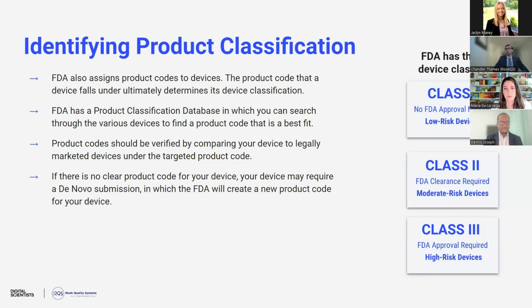Once you've identified a product code, you want to verify it by comparing it to legally marketed devices under the targeted product code. If you have one product code in mind and you look at the devices that are under that product code and they don't look like a good fit at all, you might need to consider other product codes. Now, if there's no clear product code for your device, it might require a de novo submission. This is a process which takes a bit more time than the traditional 510K pathway, but the FDA will essentially create a new product code for your device.